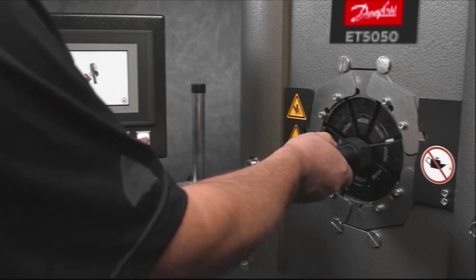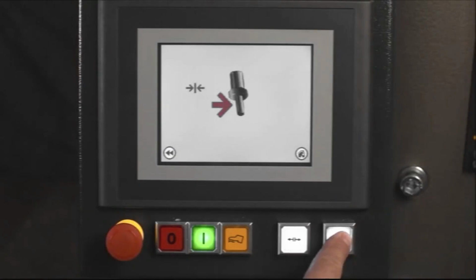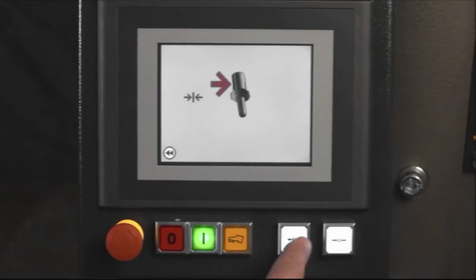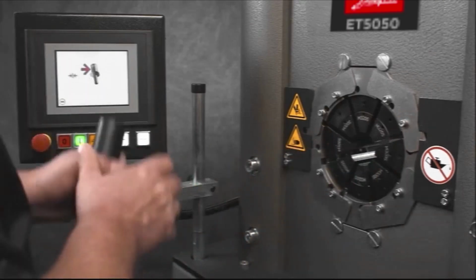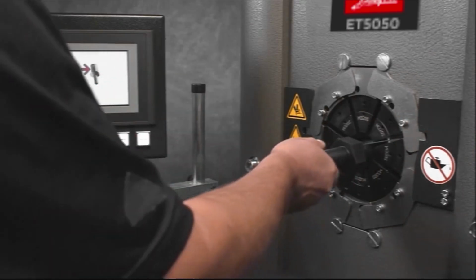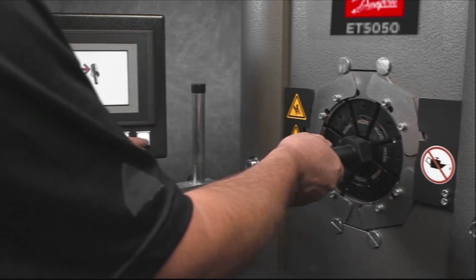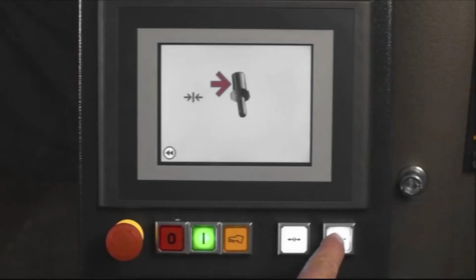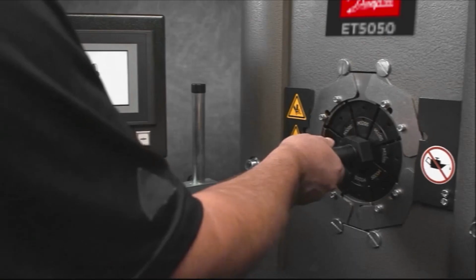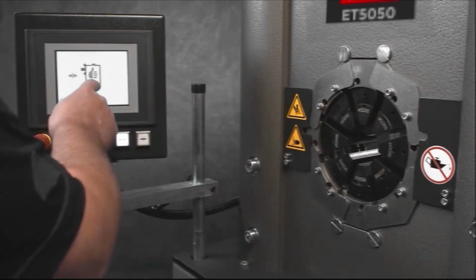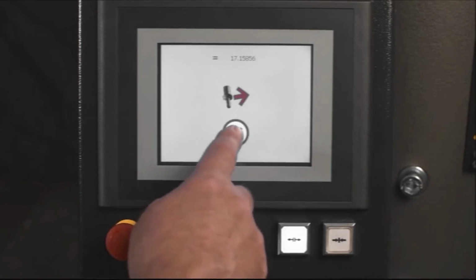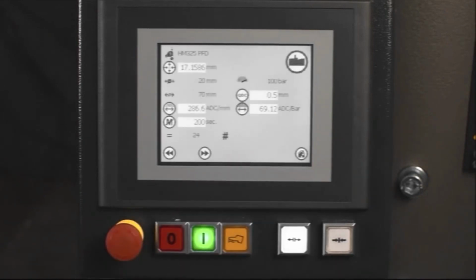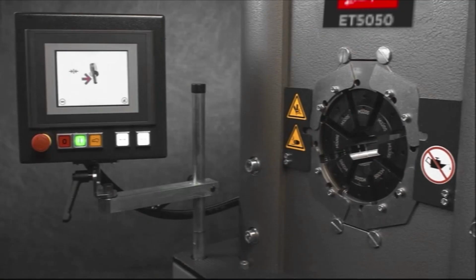Press the motor on button to start and advance the crimper head until the white light is no longer illuminated. Retract the crimper head and insert the large diameter end of the mandrel into the die cavity. Press the motor on button to start and advance the crimper head until the white light is no longer illuminated. Fully retract the crimper head and remove the mandrel. The display screen will now indicate that the calibration was successful. The ET5050 is now calibrated and ready to perform accurate and repeatable crimps.